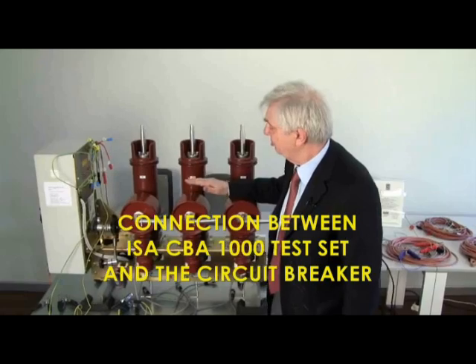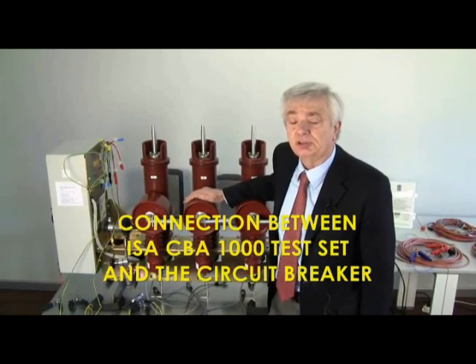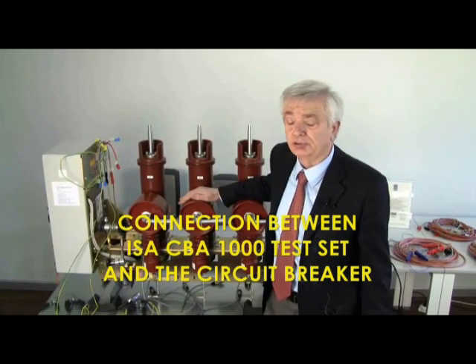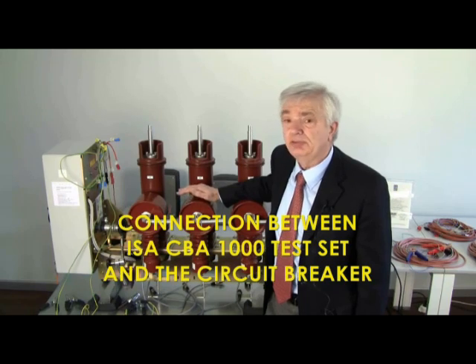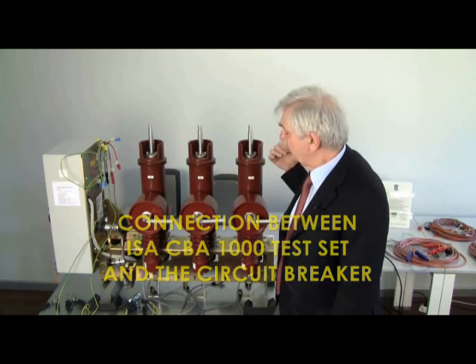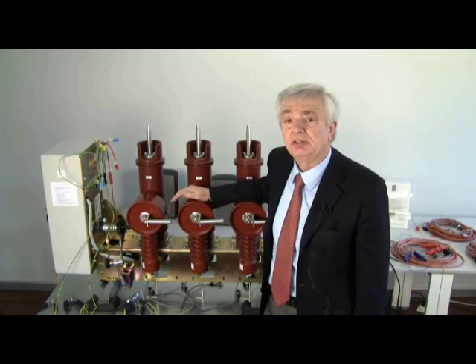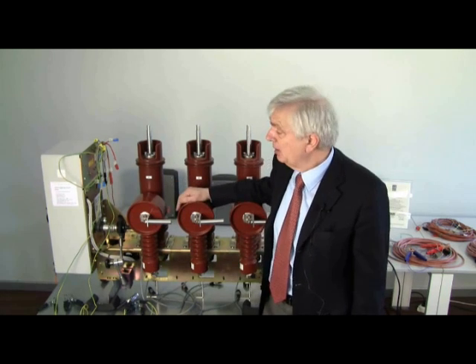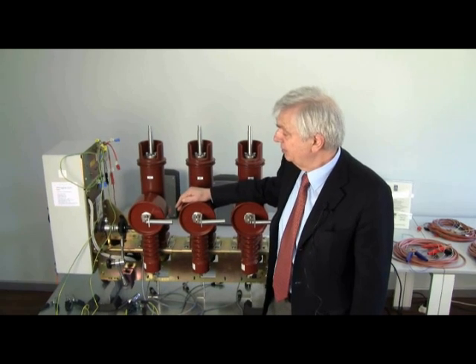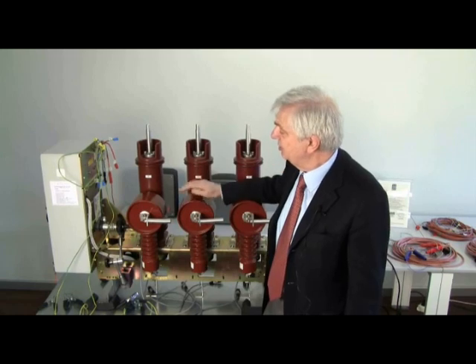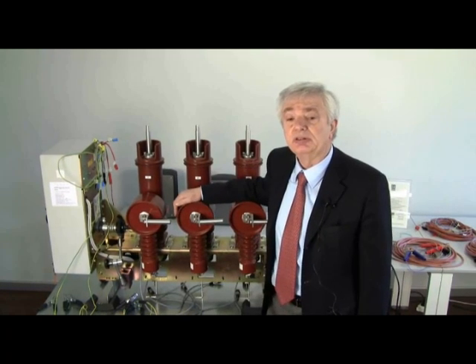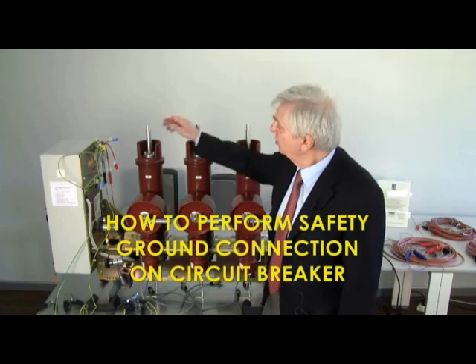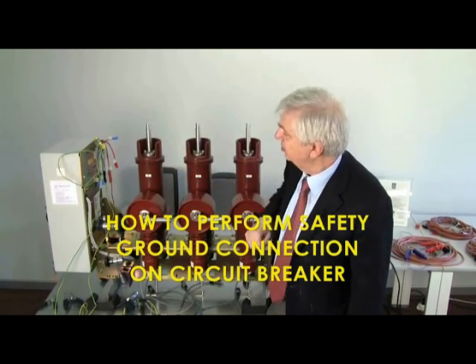You have your circuit breaker, and of course it is in service, it is closed. So the first thing that you have to do prior to connect to CBA 1000 is to open it, and immediately after, before touching anything, you have to perform a safety ground connection on both sides of the circuit breaker.